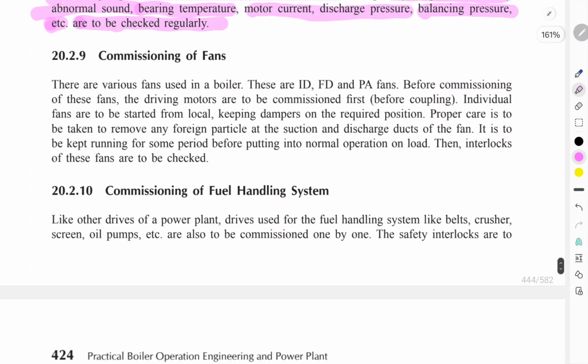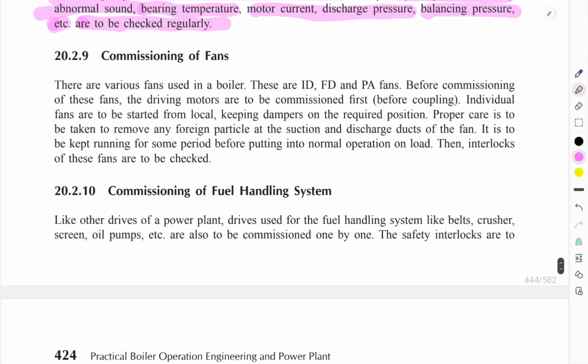Okay, commissioning of the fan. Various fans are used in the boiler. These are the FD, ID and PA fans. Before the commissioning of these fans, the driving motors are to be commissioned first, before coupling. Individual fans are to be started locally. Keep the dampers in the required position.